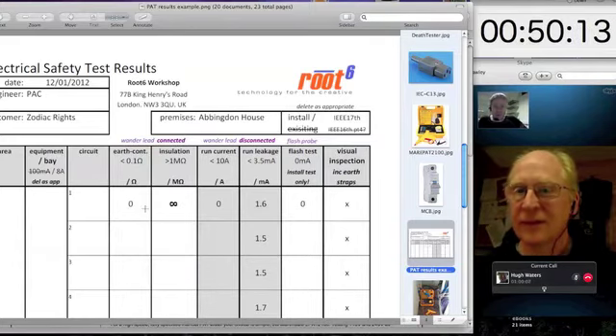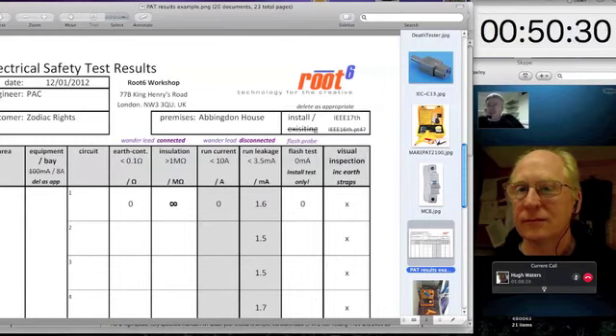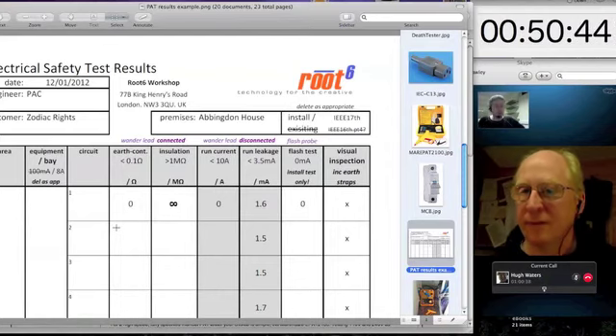and we've made sure that the mains distribution board at the top of the cabinet is turned on, and now our job is to test the 14 circuits that are being fed off that mains distribution board. And if there are 2 mains distribution boards, the other 14 or the other 12 or whatever style of mains distribution unit you like to use. So the very first thing we test for is an earth continuity test, and we'd like to see that there's less than 0.1 of an ohm of impedance between the incoming earth to the bay and the earth that reaches any piece of equipment. We'd like there to be no more than 1/10 of an ohm on the earth continuity test.